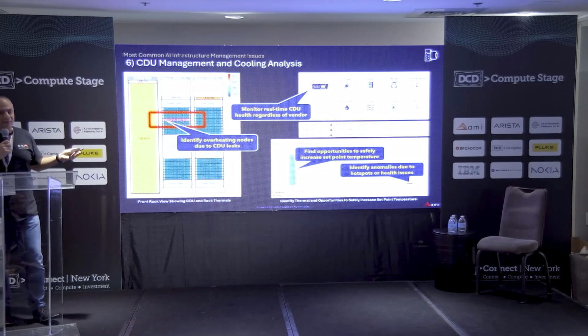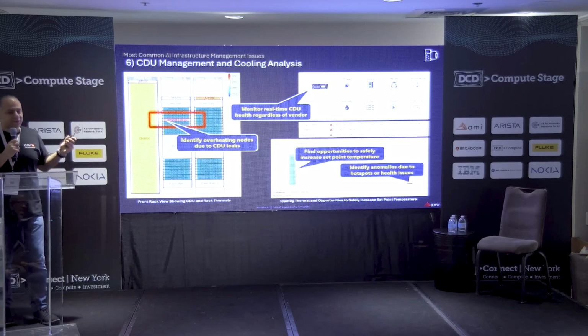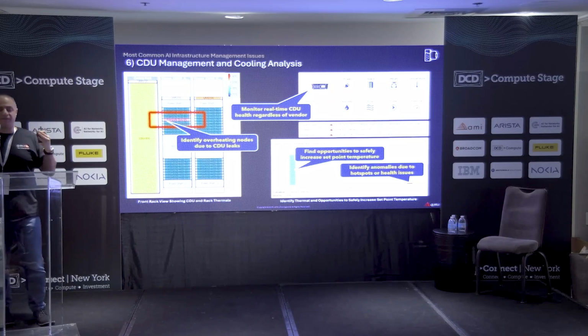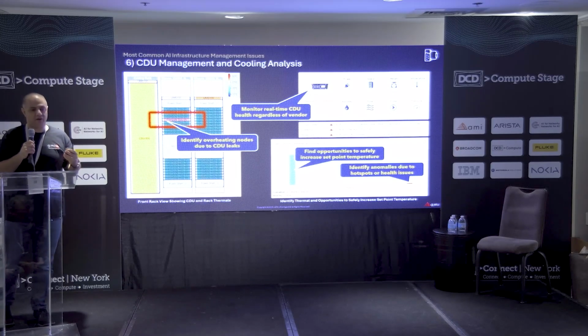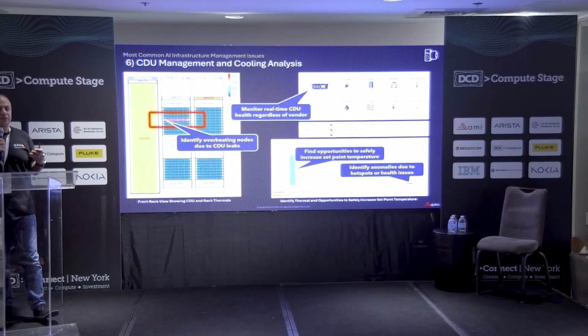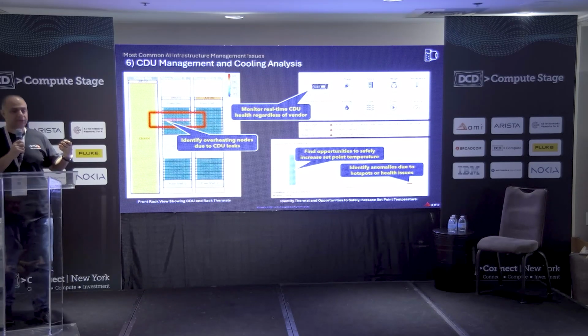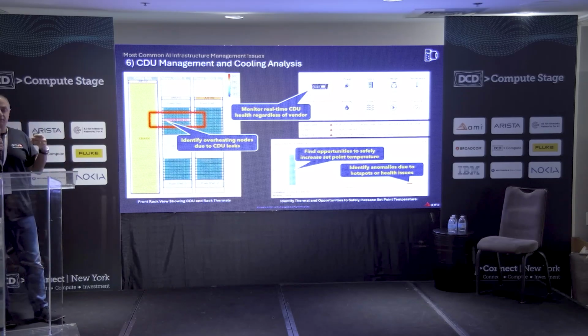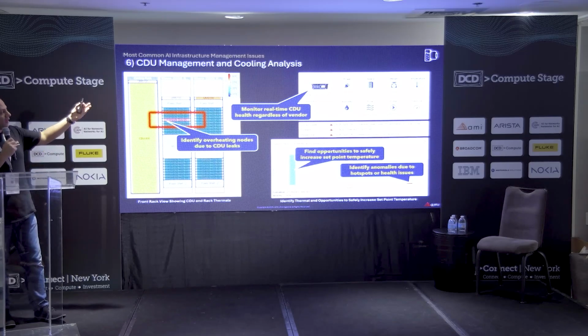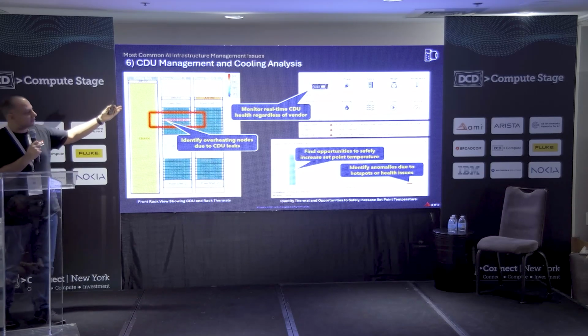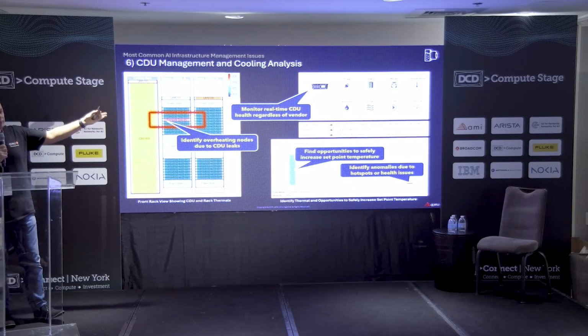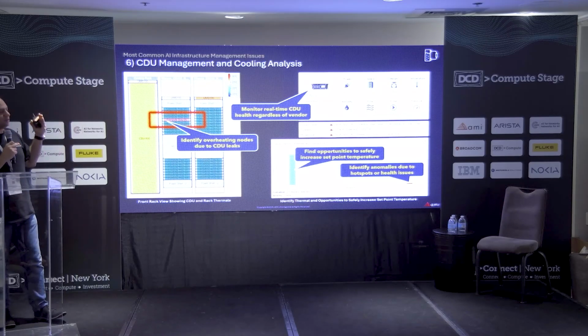Of course, you can't talk about AI without talking about liquid cooling. With all the vendors now focusing on the hardware side of liquid cooling, there's very little focus on the software management side of that. Again, DCM is really vendor agnostic. We work with a lot of the liquid cooling vendors to capture all that extra telemetry, whether it's flow rate, pump rate, reservoir levels, humidity sensors, leak detection, and that allows you to take preemptive action and shut down systems before they become catastrophic and cause massive failures.